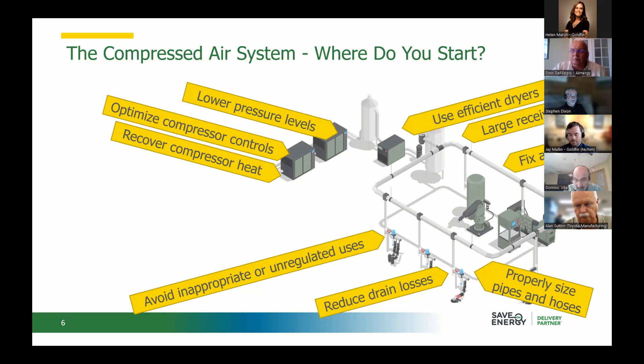But what we've just talked about in terms of the sequencing of the compressors in a multi-compressor system, or the ability of the compressor to follow the load, we can fix all the leaks we want. But if we haven't got a system that's capable of following the load downwards as it decreases because of decreased leaks or decreased inappropriate usage, we're not going to see anywhere near the same level of benefit. So we have to take a holistic, a systems level approach, meaning looking at it from one end to the other.